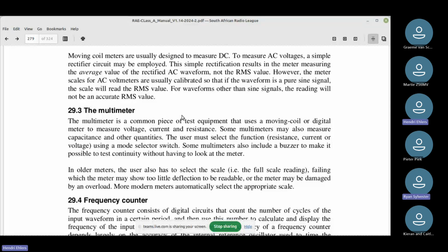And then, of course, the continuity meter, and that's something a person with a little bit of experience tends to know to look for: a meter with very good continuity measurement. If you take the two probes, put it on continuity, and touch the two probes together, the buzzer will go. But some meters only use the buzzer as a closed circuit, so the moment you touch the probes it closes the circuit and the buzzer starts. If you tap them together quickly, it's too fast for the buzzer and it does nothing.